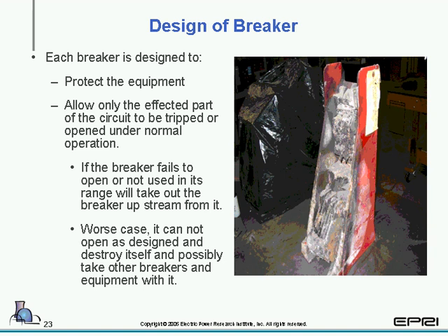Just an overview of what we just spoke about. Each breaker is designed to protect the equipment. Allow only the affected parts of the circuit to be tripped or opened under operation. If it fails to open or is not used within its range, it can take out itself or take out the breaker upstream. Or worst case, not open as designed, destroy itself, and possibly take out other equipment with it.